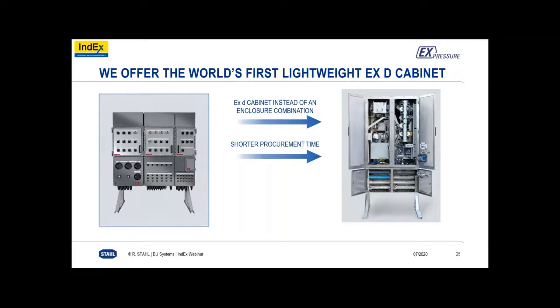By combining components in different enclosures, you have extra work in the engineering, and you also have to route your wiring from one enclosure to the other, and the construction of the switchgear is more complicated. By using ExPressure, since we have almost the size of a normal industrial cabinet, the enclosure combinations are installed in a single large volume control cabinet. As a result, you benefit in the engineering, the layout, setup, maintenance, and also inspection.